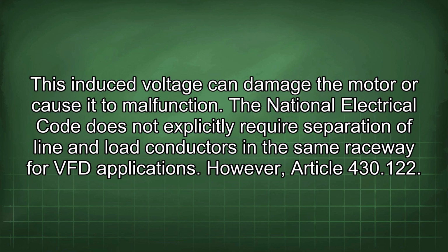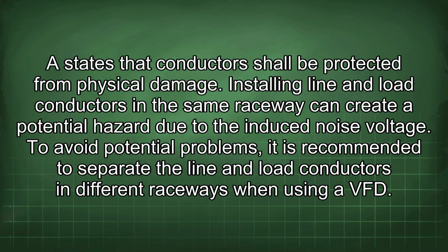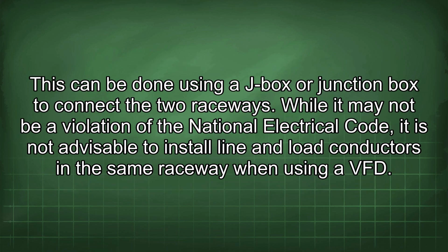The National Electrical Code does not explicitly require separation of line and load conductors in the same raceway for VFD applications. However, Article 430.122 states that conductors shall be protected from physical damage. Installing line and load conductors in the same raceway can create a potential hazard due to the induced noise voltage. To avoid potential problems, it is recommended to separate the line and load conductors in different raceways when using a VFD. This can be done using a J-box or junction box to connect the two raceways.